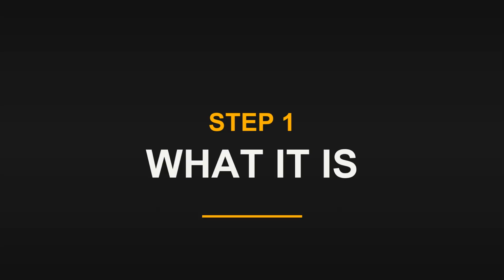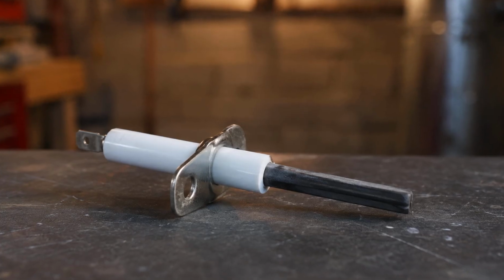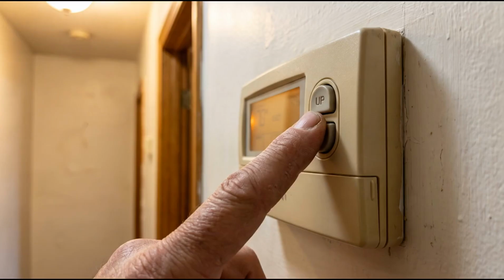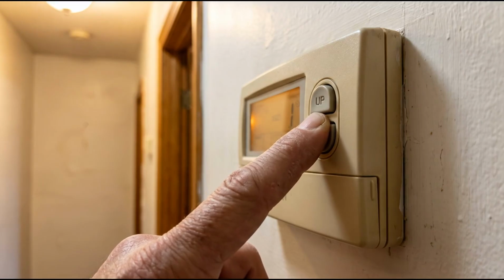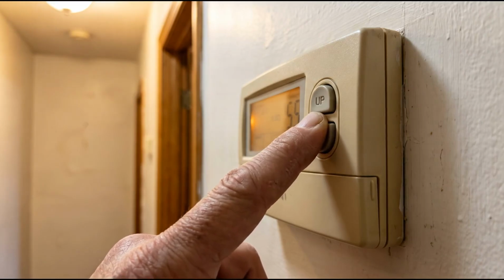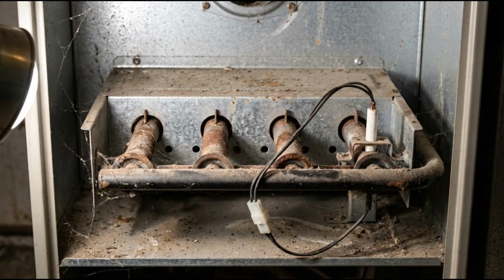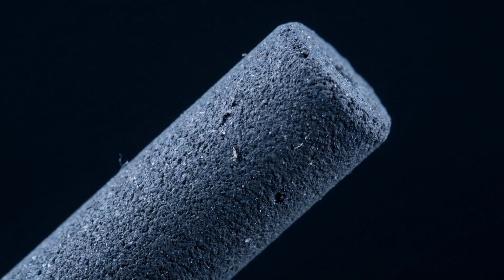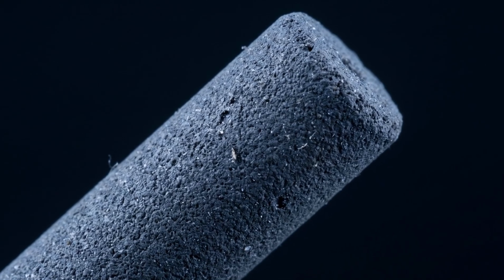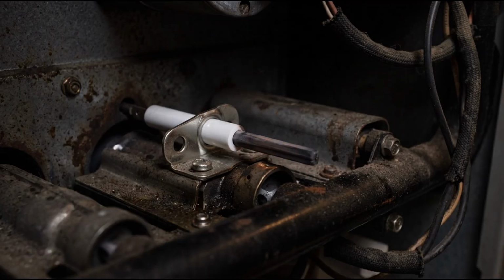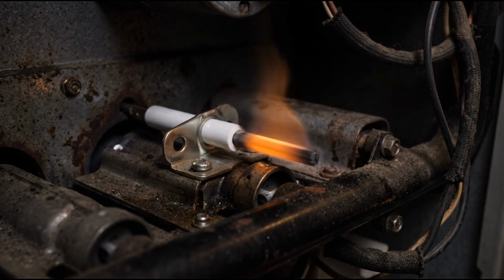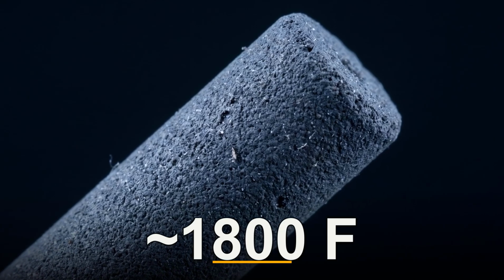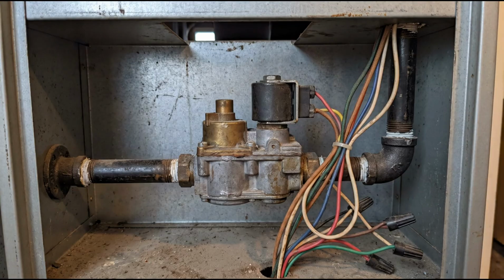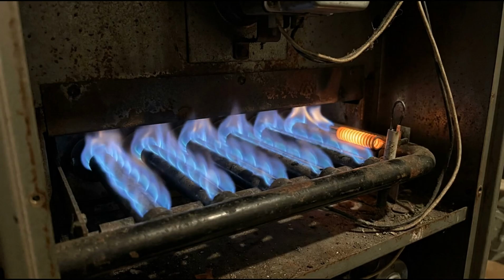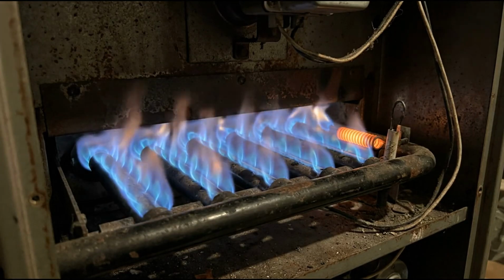Step 1. What this part is. It is called a hot surface igniter. When your thermostat calls for heat, the furnace does not use a standing pilot light anymore. Those went away decades ago. Instead, electricity runs through this small ceramic element and heats it until it glows orange, like the coil on an old electric stove, around 1800 degrees. Once it is glowing, the gas valve opens, gas flows across that glowing tip, and the burners light.